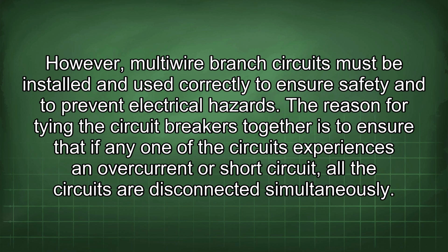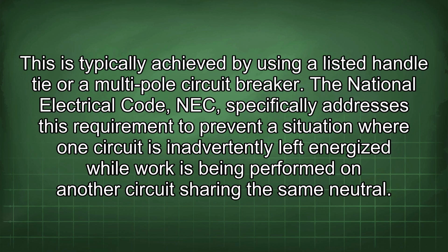The reason for tying the circuit breakers together is to ensure that if any one of the circuits experiences an overcurrent or short circuit, all the circuits are disconnected simultaneously. This is typically achieved by using a listed handle tie or a multi-pole circuit breaker. The National Electrical Code (NEC) specifically addresses this requirement to prevent a situation where one circuit is inadvertently left energized while work is being performed on another circuit sharing the same neutral.